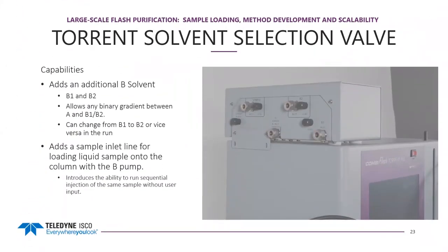The Torrent solvent selection valve not only allows automatic loading but also adds an additional B solvent. Instead of one B solvent, you now have B1 and B2. Any binary gradient can be formed between A and either B1 or B2, and you can switch from B1 to B2 mid-run. This allows a wash step at the end of the run with a stronger solvent to maintain the column. Additionally, it adds a third line — the sample inlet line for loading liquid sample onto the column — using the B pump to do this.